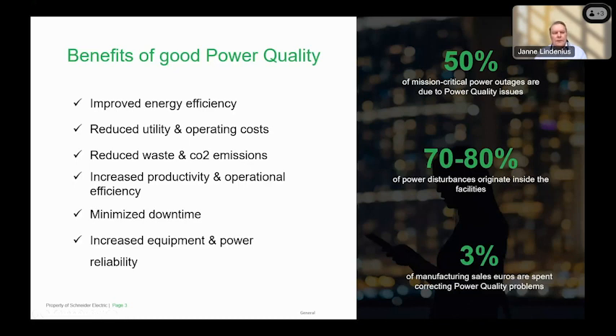Okay, why care about the power quality? According to our study, 3 to 6% of the manufacturing sales euros are spent on correcting power quality problems. Up to 50% of the power outages originate from power quality issues. Some 70 to 80% of the disturbances are born inside the facility. 8 power quality events per year is a typical number.